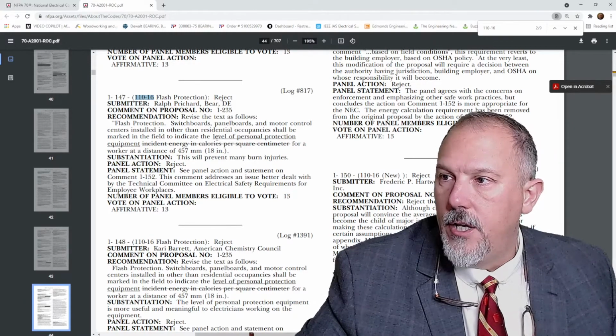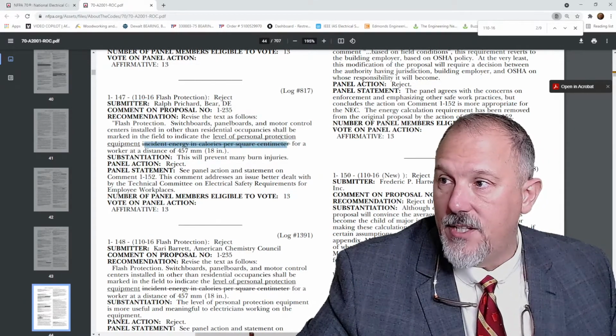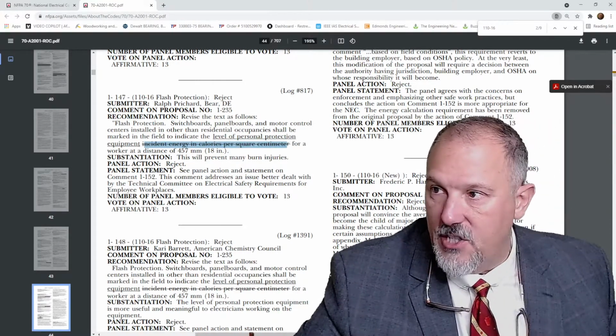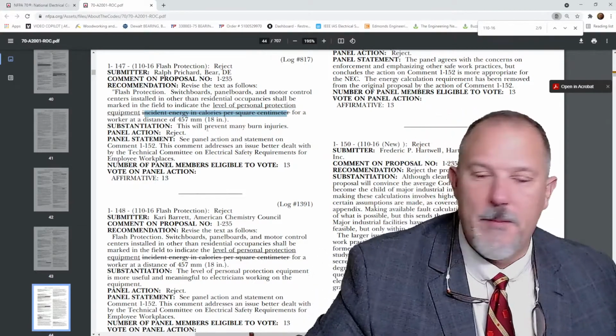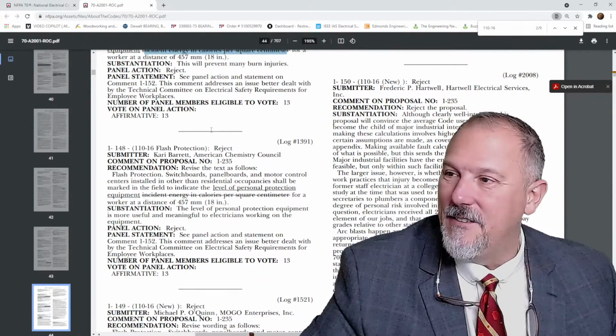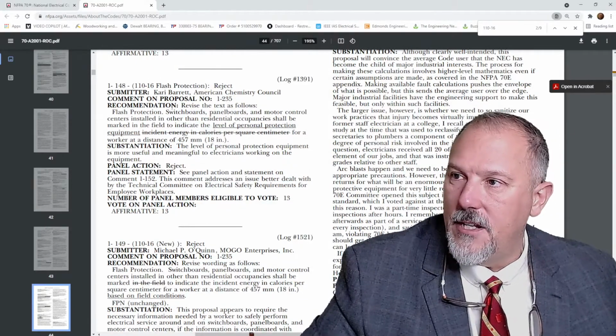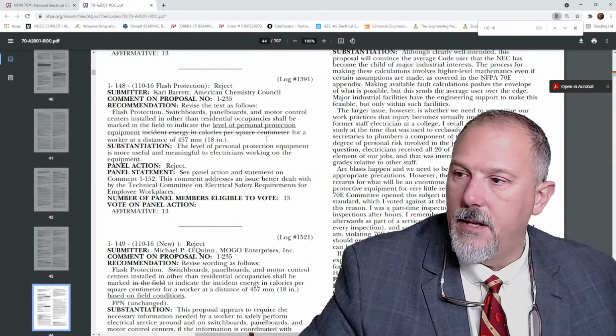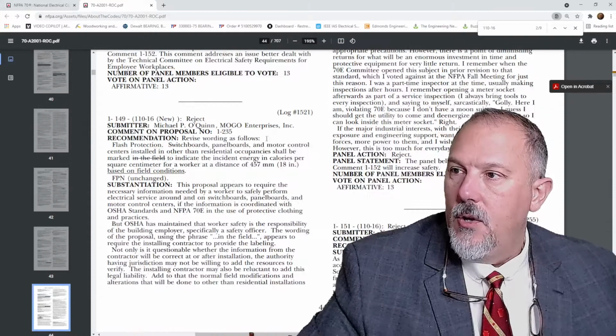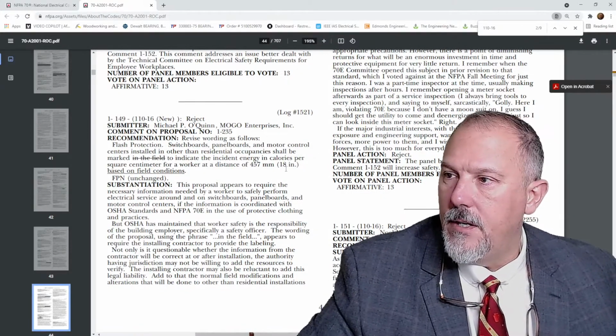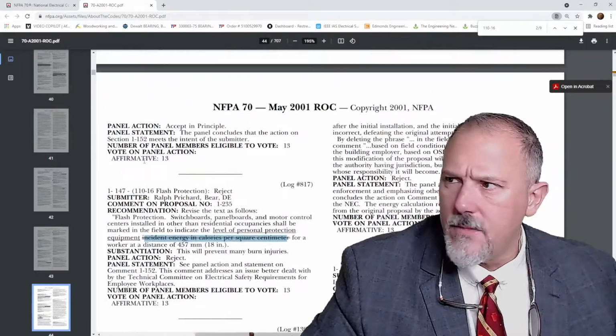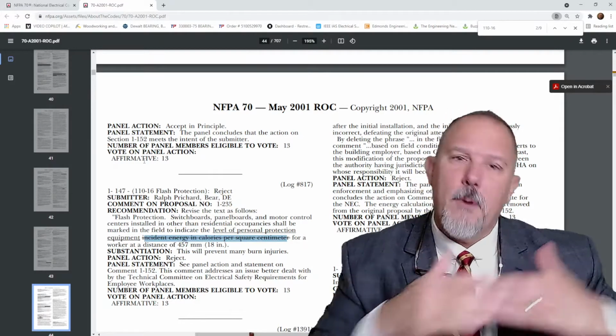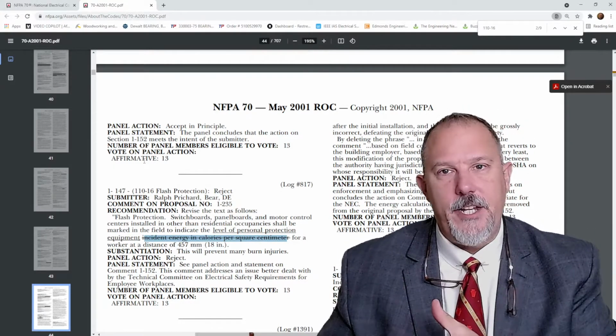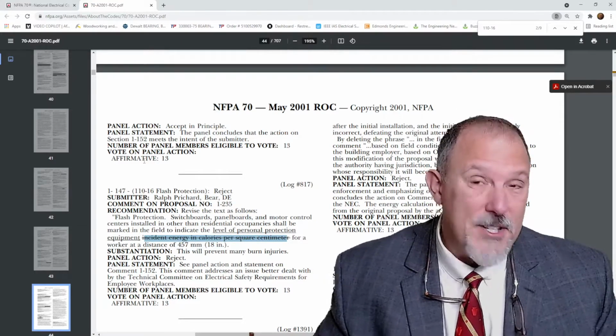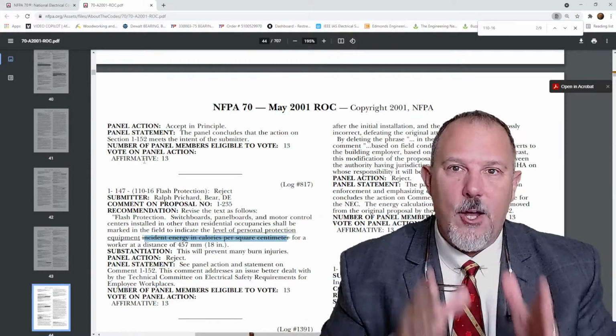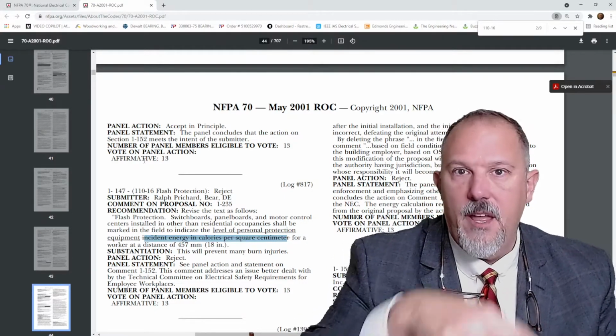This person wanted to remove incident energy calories per centimeter squared and just say level of personal protective equipment and prevent many burn injuries. Substantiation: this will prevent many burn injuries. Remember, substantiation is 99% of getting something you want into the National Electrical Code. There was another one, American Chemistry Council, who just wanted to say put the level of personnel protection. We had another, I don't know what the enterprise is, proposing 18 inches based on field conditions. So what's interesting is to read through the proposals that even failed and read through their substantiations. Sometimes they're good, sometimes they're bad. Sometimes they're accurate, sometimes they're way off base. But it helps you understand the dialogue at the time this was going in.